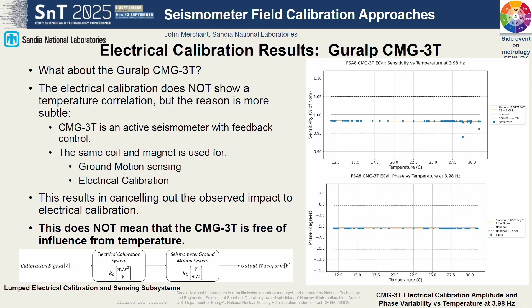And that's further compounded when we use the CalXPy results from comparing the GS13 to a CMG3T. So we're taking advantage of just the natural background seismicity. It's everything. It's the microseism, it's earthquakes, it's local, regional, teleseismic sources. And we look at these periods from CalXPy where there was high coherence and try and plot them versus temperature, and you see, first off, it's not this great SNR signal that you would see in the electrical. There's noise, there's scatter, it's less repeatable. And again, remember that this is now the lumped performance of both the reference, that we use the 3T as the reference, and we use the GS13 as the sensor under test.